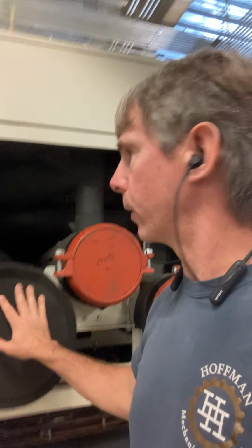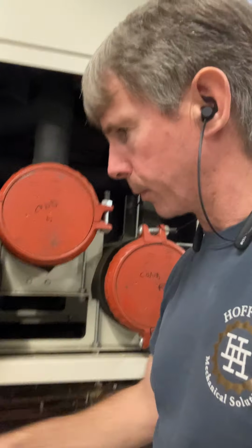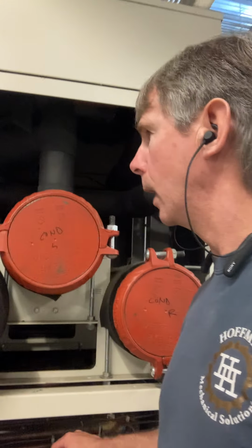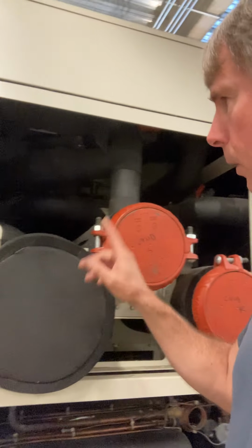We're going to have chilled water return coming back to the chiller at 54 degrees. We're going to route that 54-degree water down to this evaporator. The compressor comes on, and it's going to cool that water down to 44 degrees, somewhere in that range. That cold water goes back up into the other pipe, goes down to the end where it then leaves the chiller and is pumped out to the building.